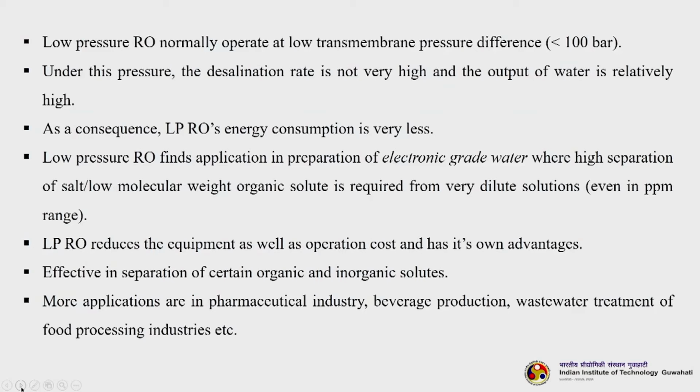Now, low pressure RO normally operates at low transmembrane pressure, less than 100 bar. Under this pressure the desalination rate is not very high, however the output of water is large. As a consequence, low pressure RO's energy consumption is very low. Low pressure RO finds application in preparation of electronic grade water, which is used in electronics industries, where high separation of salt and low molecular weight organic solute is required from very dilute solutions, even in the ppm range.